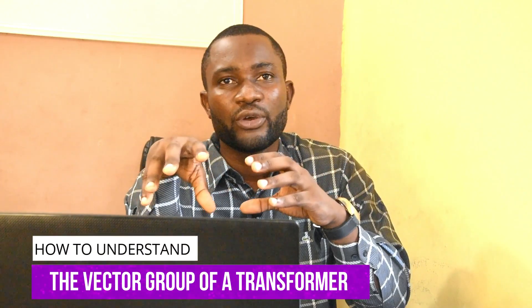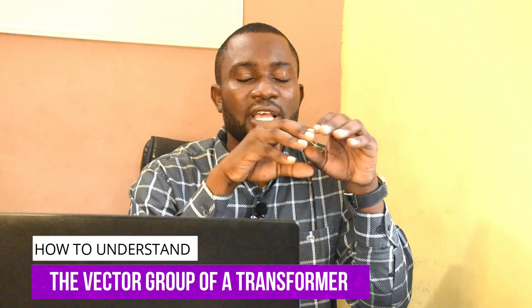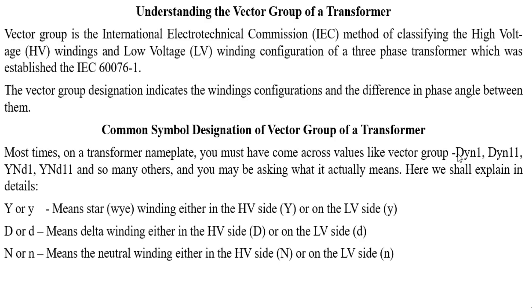In your transformer, we normally have name plates, and the name plate is represented with symbols. If you don't understand what those symbols actually mean, you might not be able to know what the vector group configuration is. In IEC 60076-1, which is the standard that covers vector group configuration of the transformer, on the name plate you will see something like DYN1, DYN11, YND1, or YND11.